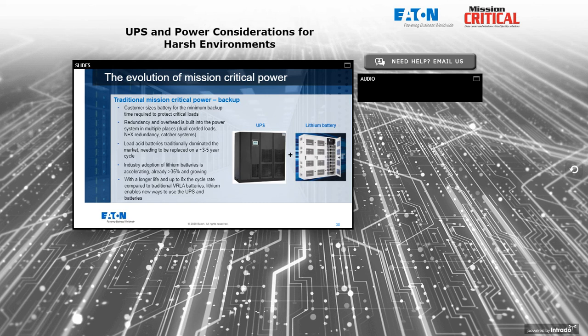So let's talk a little bit about the evolution of mission-critical power. UPSs in general have been there to basically wait for the next power outage and bridge the gap while the generator starts up out in the backyard. Maybe in the meantime, they provide power conditioning, voltage regulation, frequency regulation, power factor correction, et cetera, in the form of power conditioning for the client.